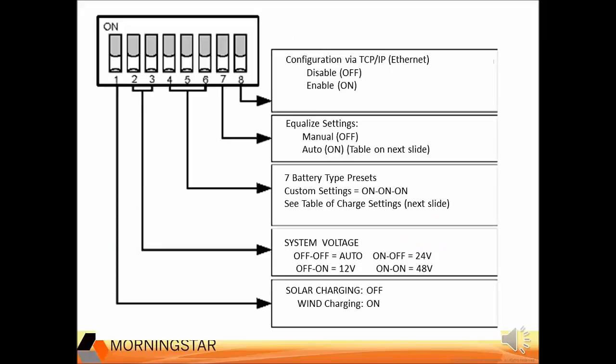This is the breakdown of the TriStar MPPT DIP switch settings. Starting with the switches that were enabled in the previous slide, switch eight enables the Ethernet write commands. We made it possible to disable this as a security measure so someone can't connect to the controller remotely and change the settings. The program custom settings are enabled with switches four, five, and six on, and there are also seven factory presets that will be shown in the next slide.